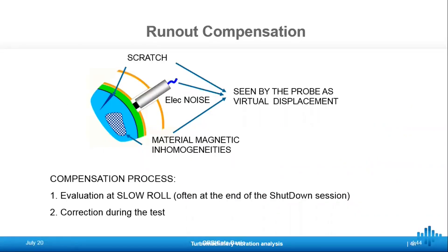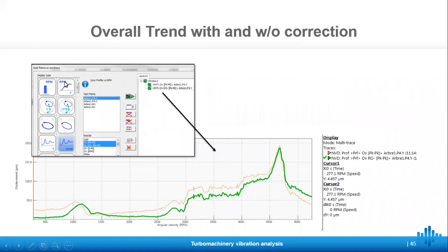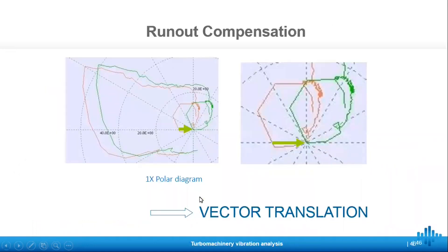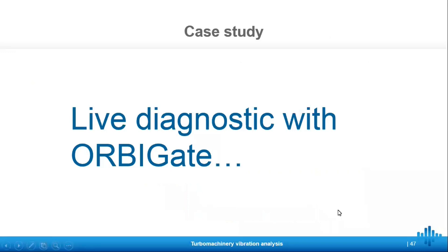The last key feature is run-out compensation. Sometimes the probe sees displacement that may actually be caused by things such as scratches, electrical noise, or magnetic inconsistencies rather than actual displacement. We would like to subtract that noise out of our data so that all we are left with is the real displacement. In the software, it's possible to set a low speed slow roll — that low speed data is used for vector subtraction in order to compensate the run-out and get rid of the noisy displacement. Now let's go over to Luke for a live demo of how this all works.